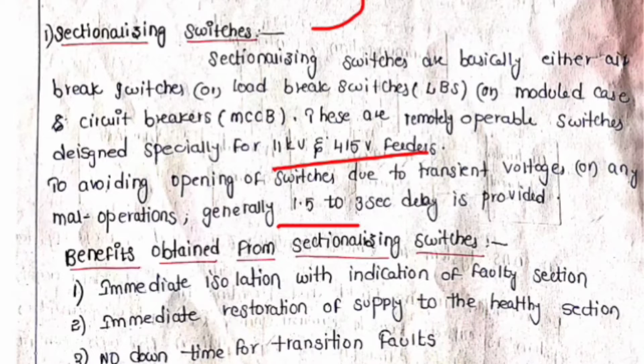To avoid opening of switches due to transient voltage or any maloperation, generally a 1.5 to 3 seconds delay is provided for sectionalizing switches. If the fault is temporary in nature, due to wind or any object or bird falling on the line, then it can be automatically closed; that is where sectionalizing switches play an important role. If the fault continues for a longer time, then it will give a signal to the circuit breaker to trip. That is the purpose of sectionalizing switches. The benefit obtained from sectionalizing switches is immediate isolation with identification of the faulty section.